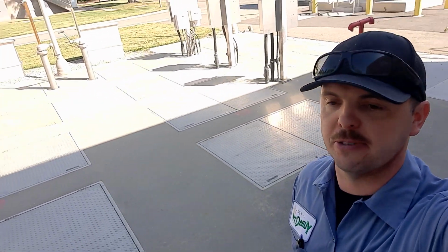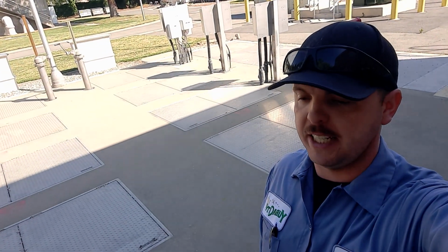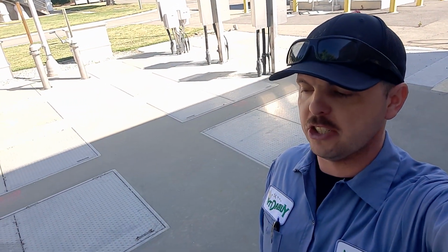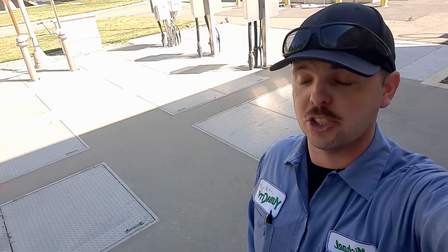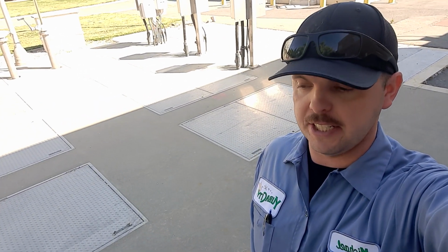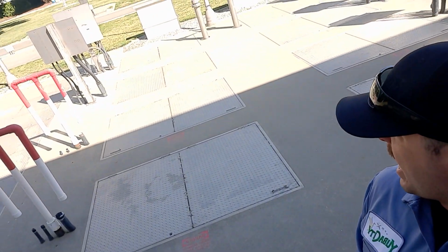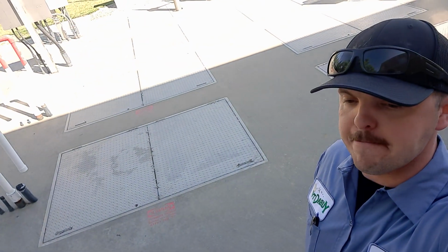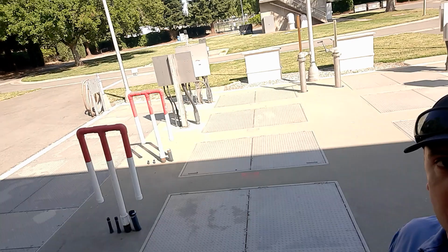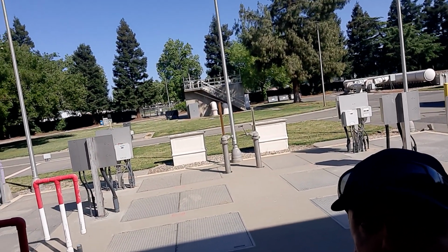Removing rags from the wastewater is important because rags will bunch up, they'll clog pipes and destroy pumps, motors, what have you, so removing those rags is a pretty crucial point. So past the bar screens, the water will flow into this giant sump right here, and down that sump we have six different lift pumps, and they'll lift it into that structure that you'll see behind me, which is our grit aeration chamber.